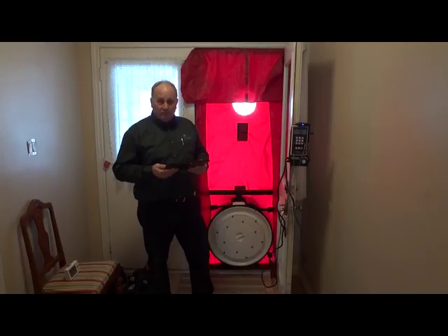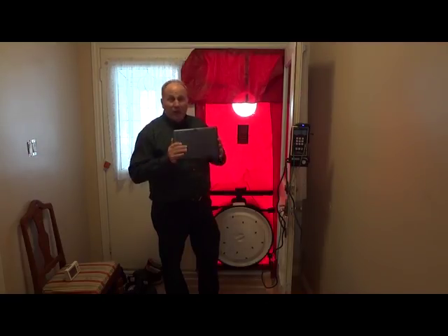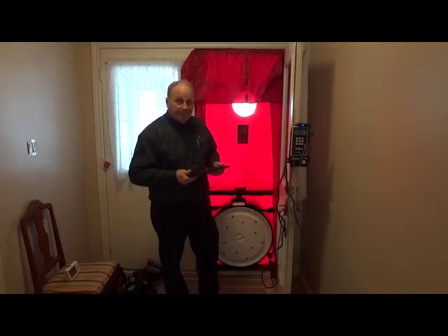And further to Tom's testing, he has an estimated leakage area of about 30 square inches. So this means if we added up all the cracks and all the air leakage in his home, it would add up to a 10 by 3, about the size of this tablet that he has, as air leakage, which again is very, very good. Good job, Tom.